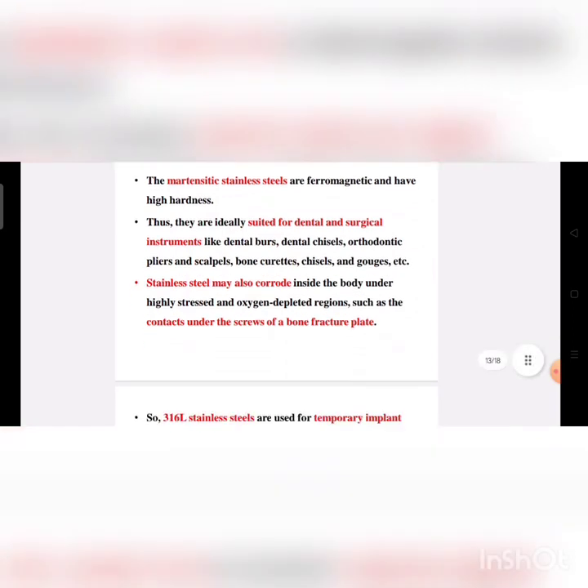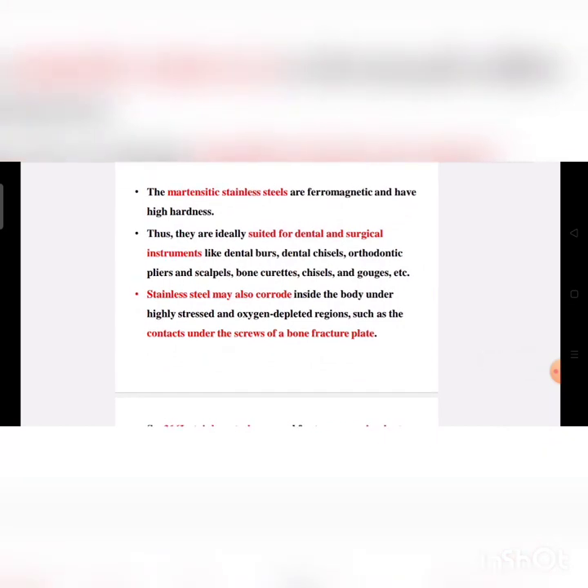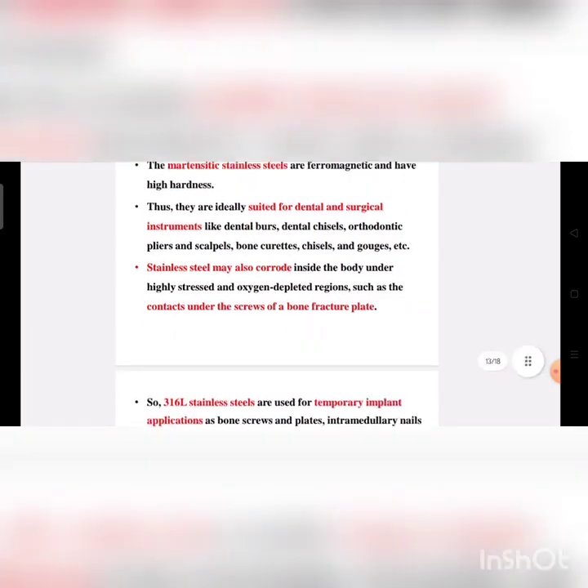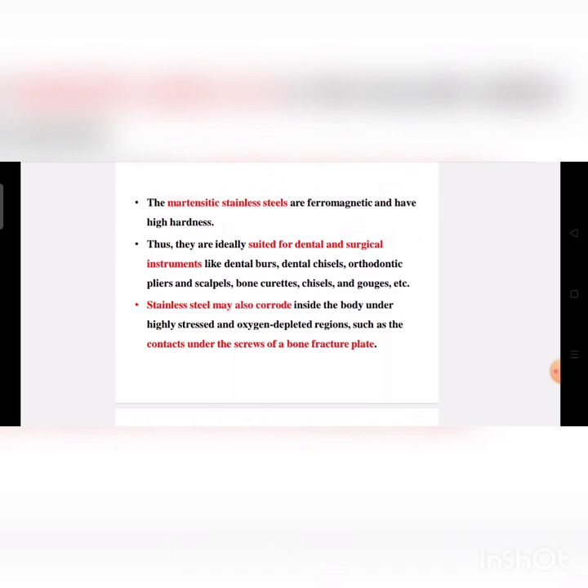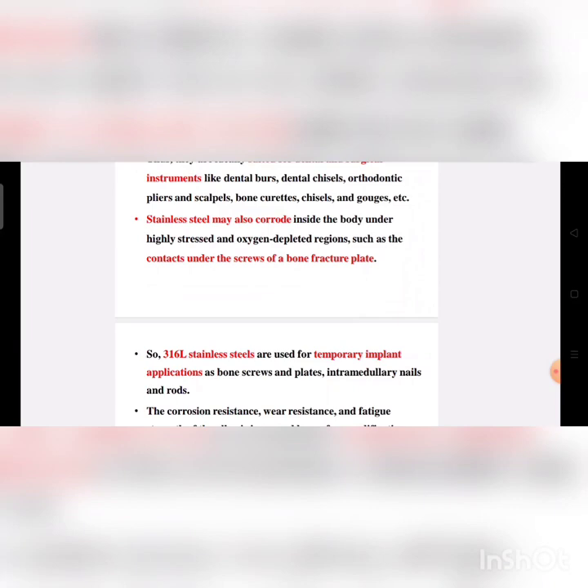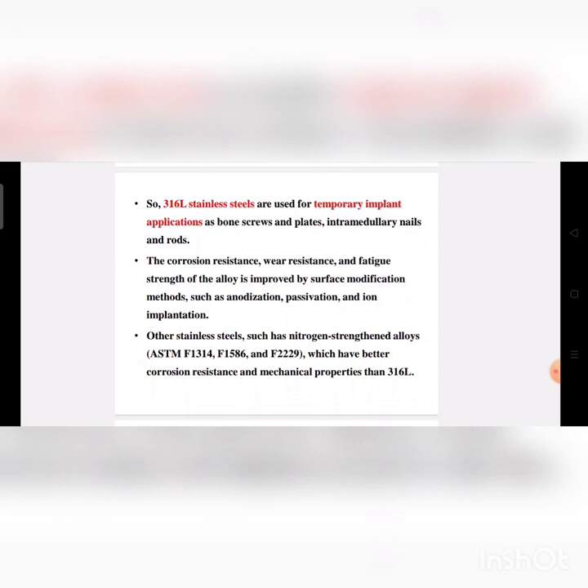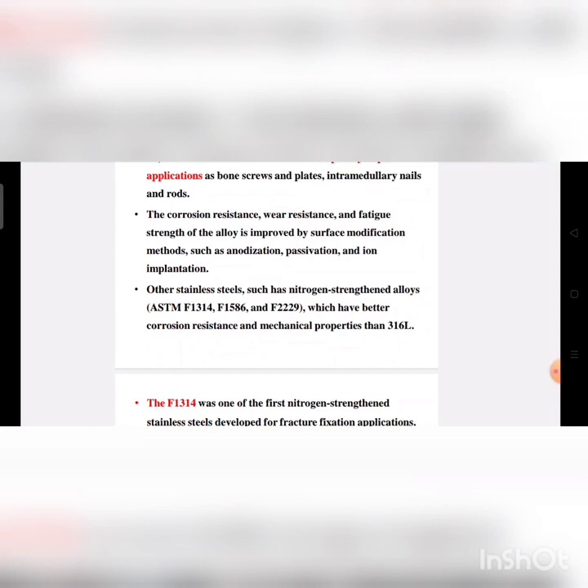The martensitic stainless steels are ferromagnetic and have high hardness, making them ideally suited for dental and surgical instruments such as dental burs, dental chisels, orthodontic pliers, scalpels, bone curettes, chisels, and gouges. Stainless steel may also corrode inside the body under highly stressed and oxygen-depleted regions, such as the contacts under the screw of a bone fracture plate. It is mainly used at load-bearing sites. These steels are also used for temporary implant applications — bone screws and plates — which are not permanent. The corrosion resistance, wear resistance, and fatigue strength of the alloy can be improved by surface modification methods such as anodization, passivation, and ion implantation.